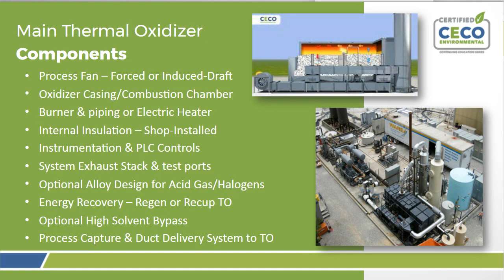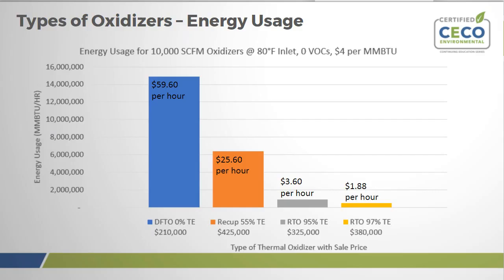So just before getting into the different oxidizers in more detail, I want to direct your attention to this graph. This shows energy usage in million BTUs per hour, a common unit, for 4 different oxidizers, but they're all 10,000 SCFM, and we're assuming 0 VOCs. And it's important again to note that VOCs are a fuel source. So whatever heat you don't add to the system in VOCs, you have to make up with your fuel. If you have a lot of VOCs, you don't need to add as much fuel, because essentially you're just maintaining a system at a certain temperature. So you can see the difference in fuel efficiency is really vast.